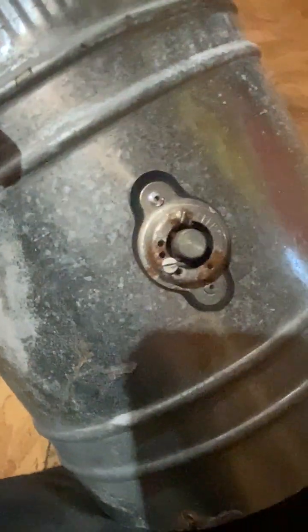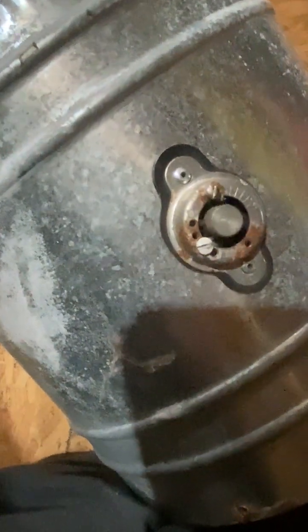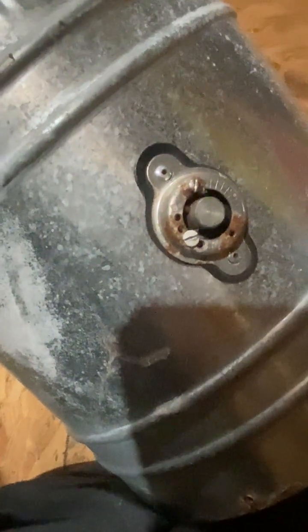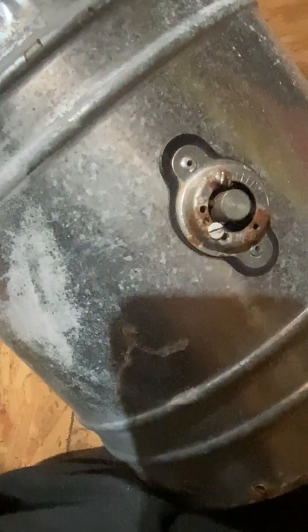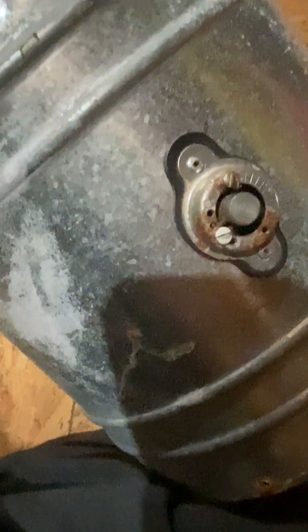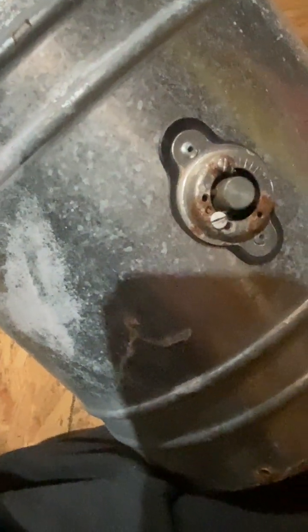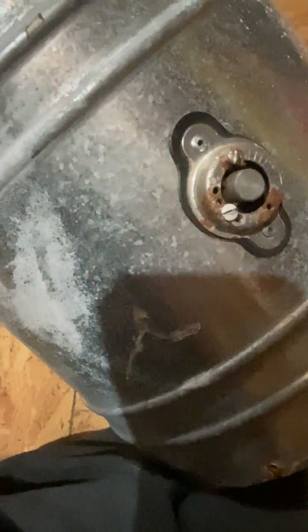You also notice that the other end of it, the rod that goes through it, comes out the other end. And interestingly enough, and probably not known by a lot of people, you can set these things for how closed or open you want them by moving one of those screws. You see how as I'm moving the inside, it moves around and it hits this peg that says that's fully closed. But say you had a situation where you wanted it to be, this is fully open, this is partially closed, this is a little more closed, and this is full. You can take that screw and move it so that fully closed is not really fully closed. The motor will power it around to this position and leaves it somewhat open.